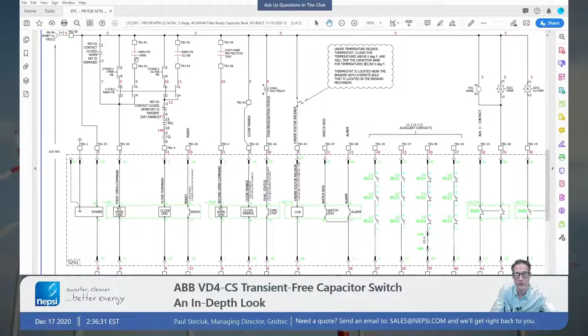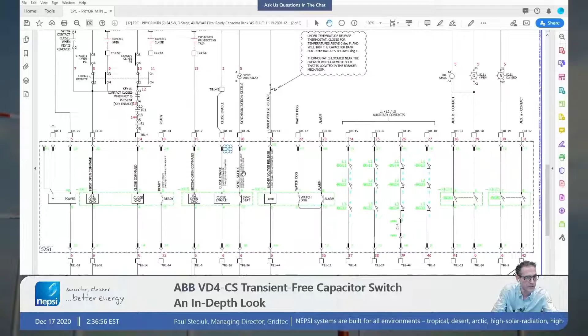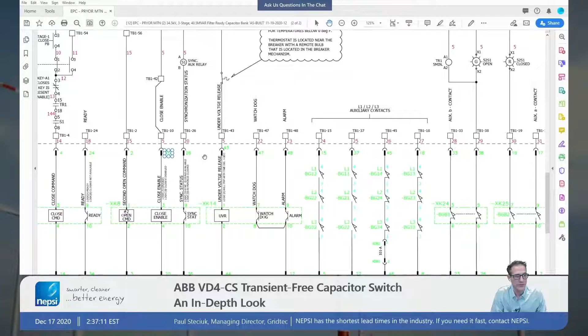You can see there's a push button up here to close. And we also use an interlock scheme for that, and we do a remote open through SCADA, so we're allowed to do that there. You can do the same with the close here. We have a close command coming through here, and that's done through remote SCADA or done through a local command here. There's a close enable which we have jumpered out, but we could use that close enable for any given function. And then we have sync status. The VD4-CS has the ability to monitor for sync status. Is it synced with the system? Are we going to be doing 0 voltage closing? And we have the ability to prevent the breaker from operating if we don't have synchronization in the closing direction.